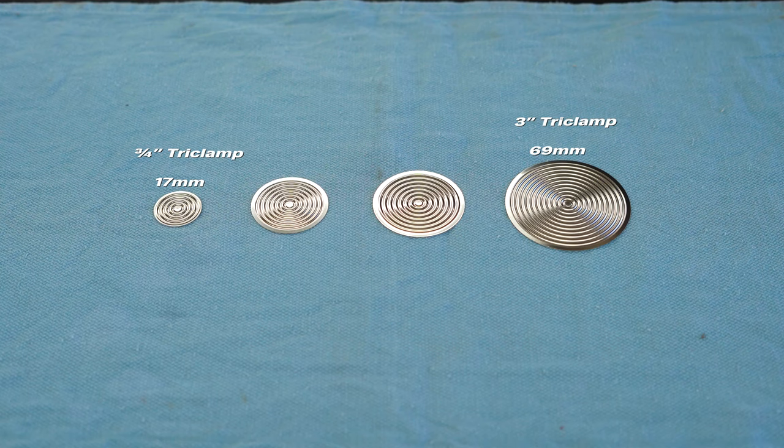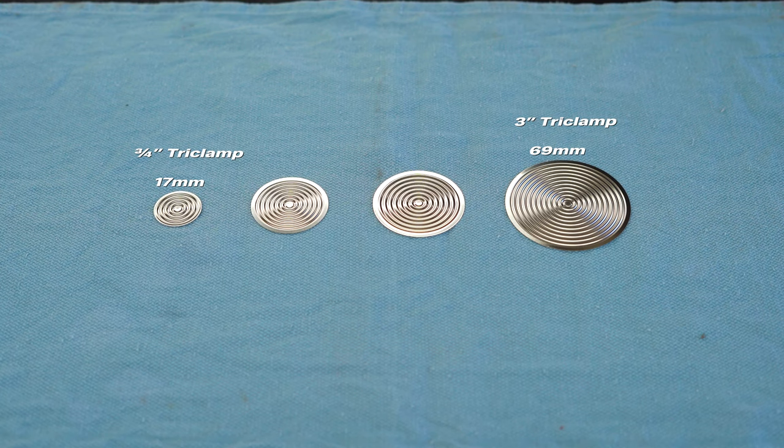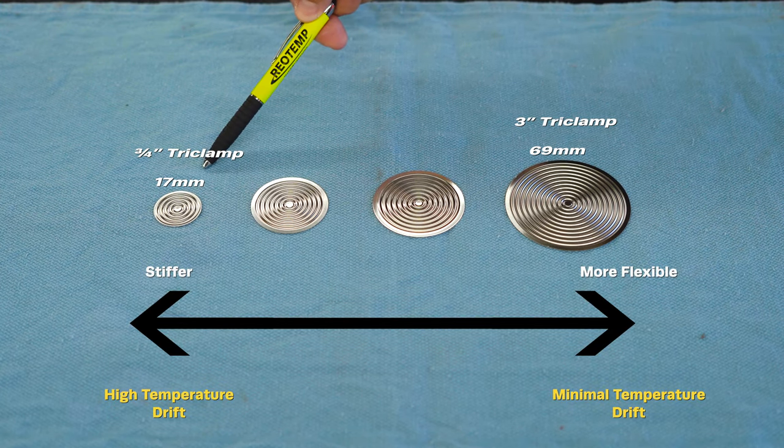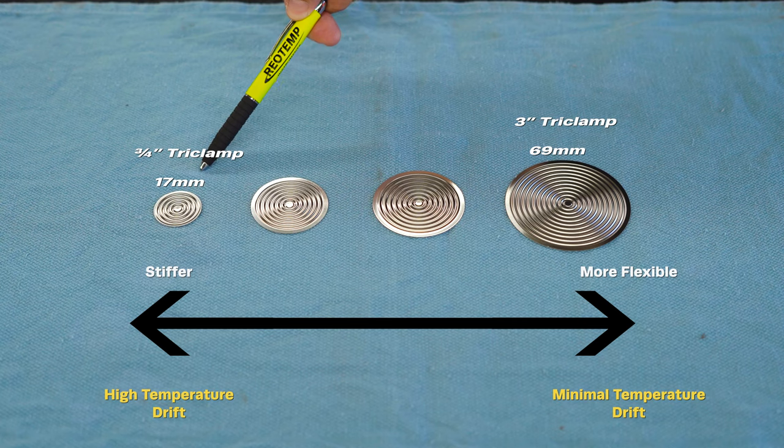If the diaphragm is flexible enough, it absorbs the small change in fluid volume. Stiffer diaphragms cannot absorb the volume change and result in an incorrect pressure reading. This is also known as temperature drift.